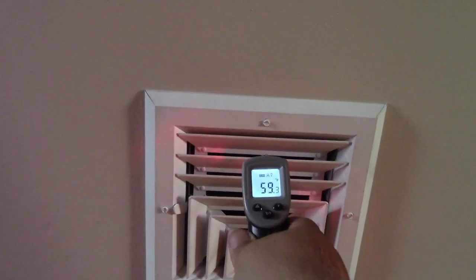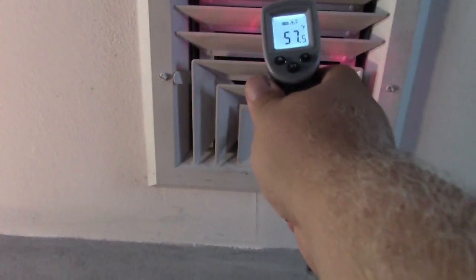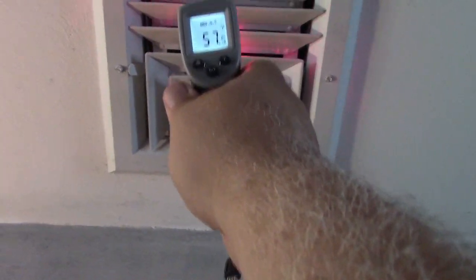We're reading 120-ish — 121. Let's go upstairs and see what we're getting. The return is reading 75 now, that's down from 80. And the vent — the vents in here are not the coldest for some reason — 59, 60. When that runs for longer, we should get even colder. Let's check the other room — 57. That's a couple degrees cooler, which is about right.